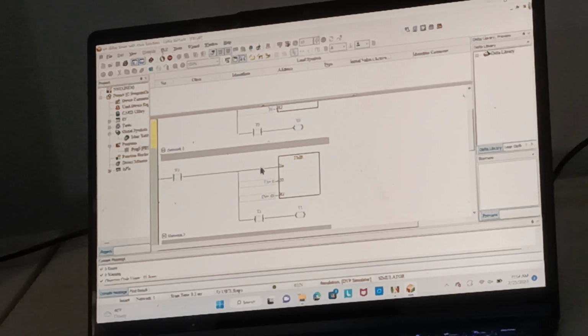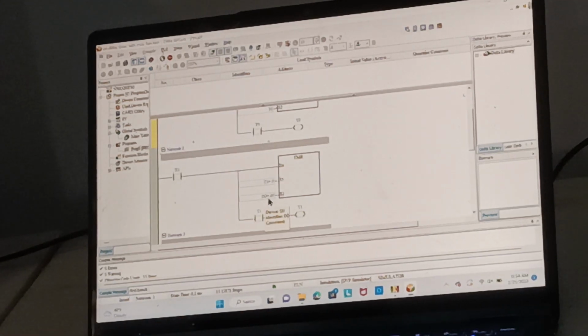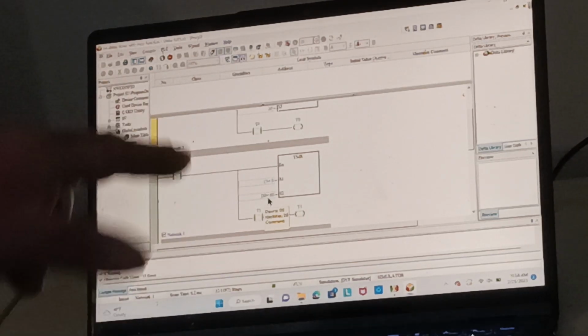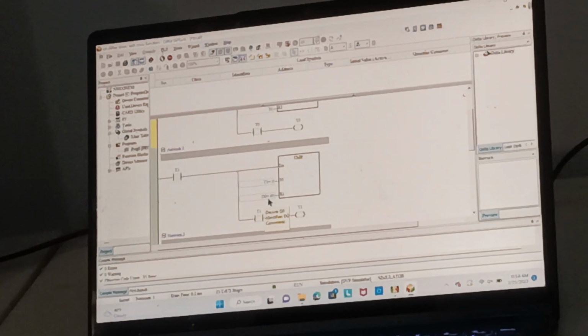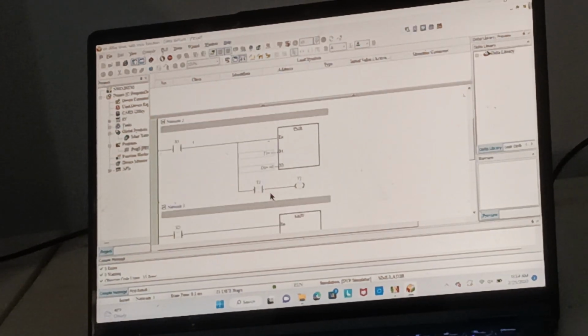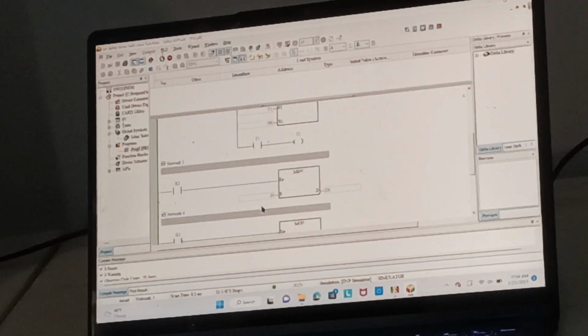So that's why sometimes if you want to be able to change something, you use this data register here. Rather than putting 30, I put D0, and when I went into online mode, it just went with the last value that it had. That's why I had it offline, to show you what you're going to see. If you get a printout of what's going on in the PLC, you'll see that D0, you won't see that it equals anything. Well, this is the program happening. So let's see, our timer right now is set for 6 seconds, and that's simply because the last one I had pushed was this move function for 6 seconds, but it just goes with the last one we pushed. So let's push this one for 2 seconds.